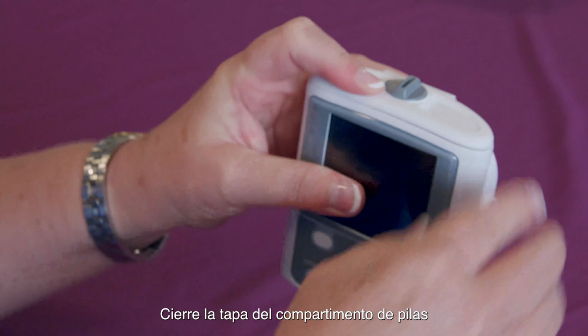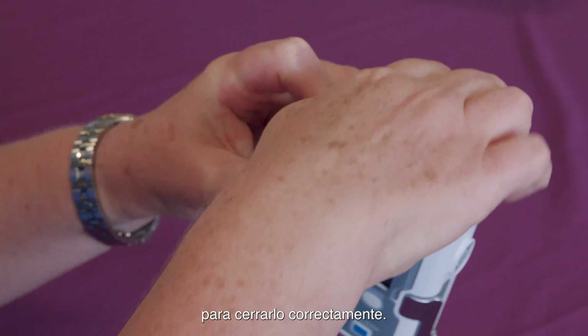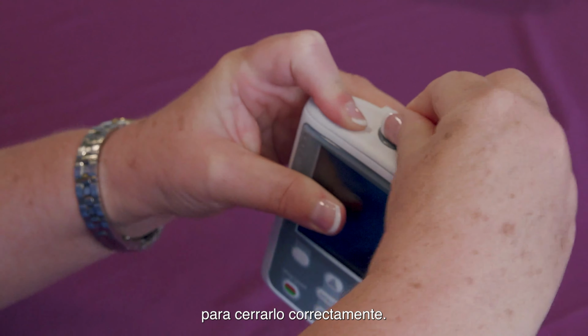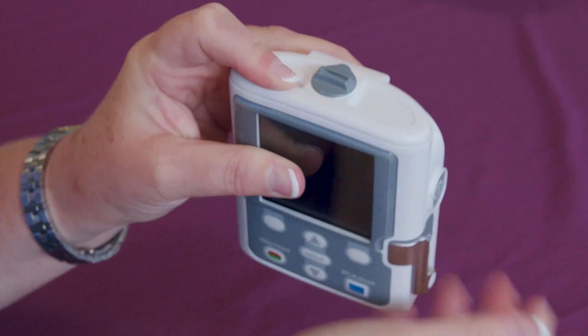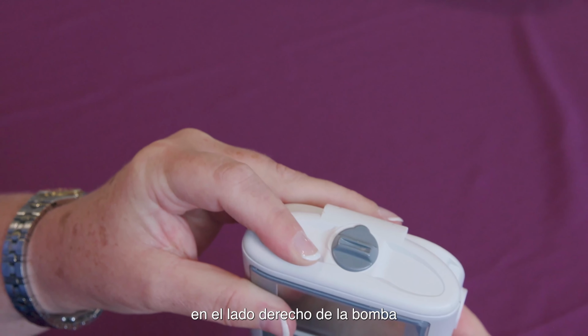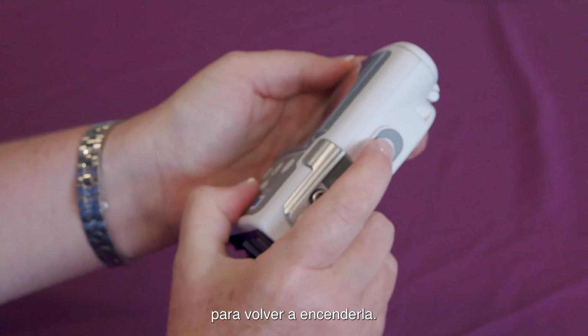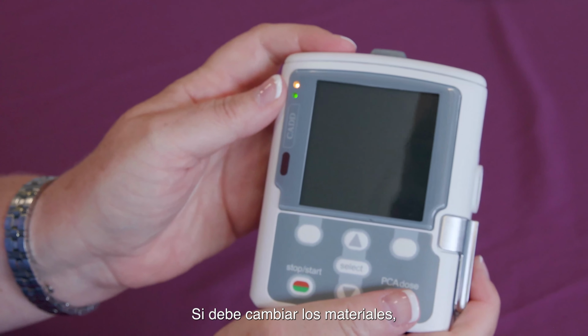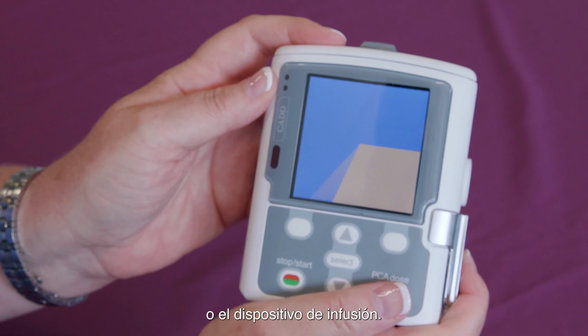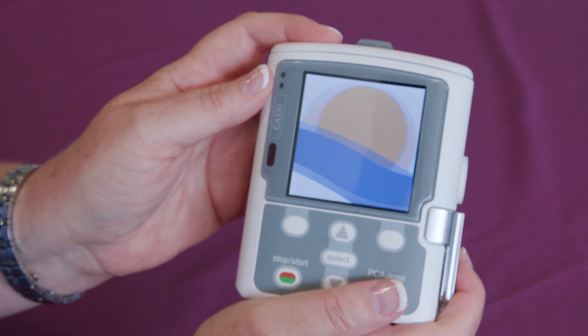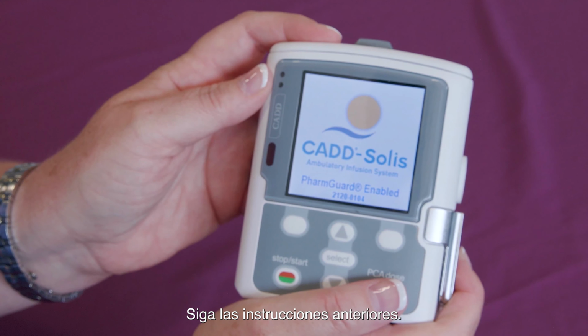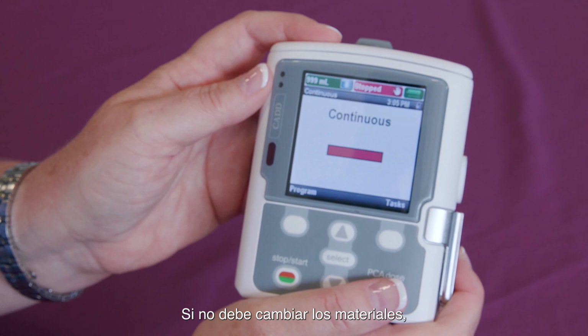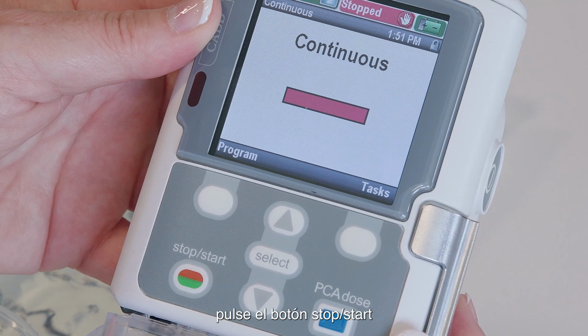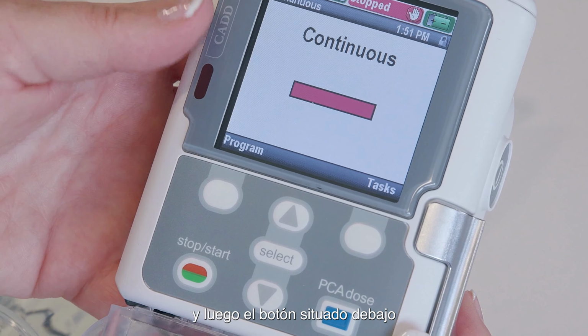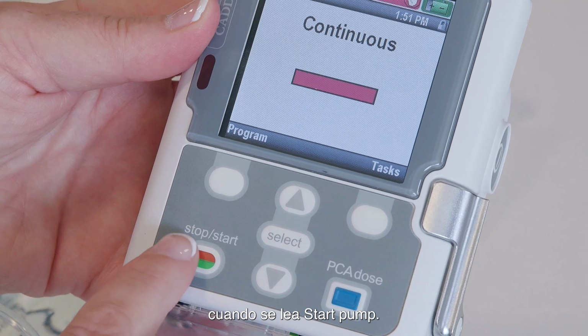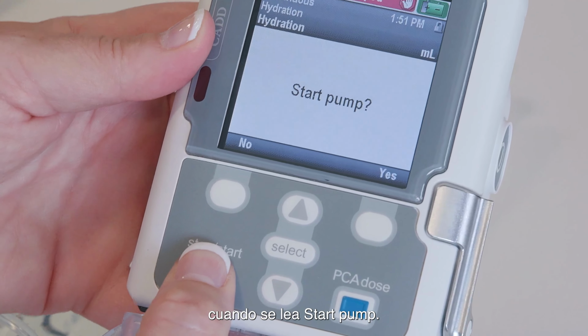Close the battery door and turn the knob clockwise to secure it shut. Press the power button on the right side of the pump to turn the pump back on. If you are changing the supplies, this would include your medication bag or tubing. Follow the previous instructions. If you are not changing the bag, press the Start-Stop button, then press the soft key under the word Yes on the screen when the pump reads Start Pump.